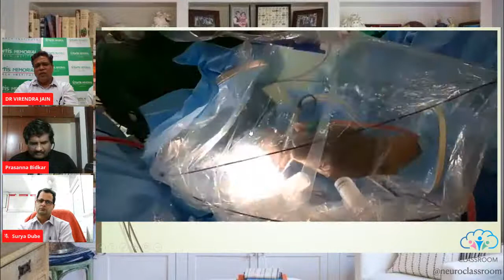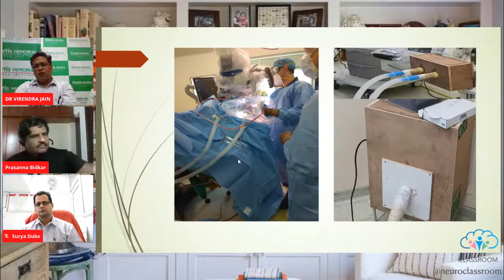Now I'll be highlighting this negative pressure suction tube which you can see. This suction tube is then connected to this source, which is then connected to a high pressure negative pressure suction, specially built by our biomedical team. So this provides extra negative pressure suction, so that all the aerosol generated in the operative area is negatively aspirated and thrown out of the system, so that the exposure of the aerosols to the other healthcare workers is minimized.